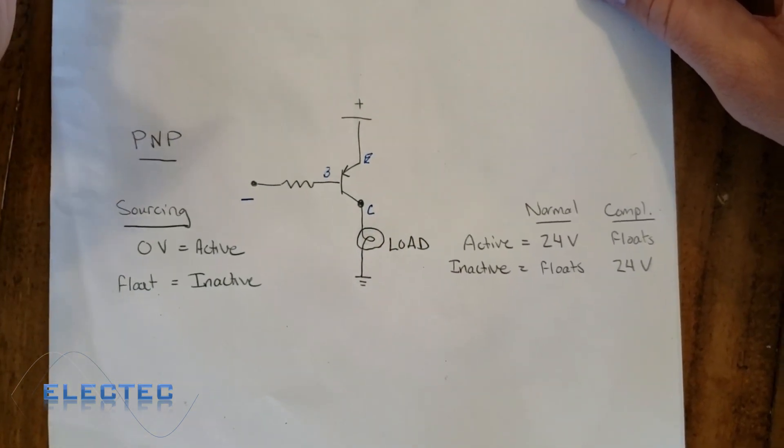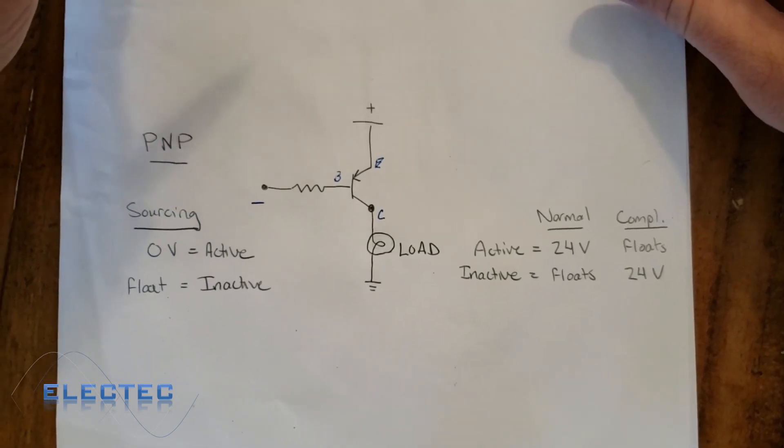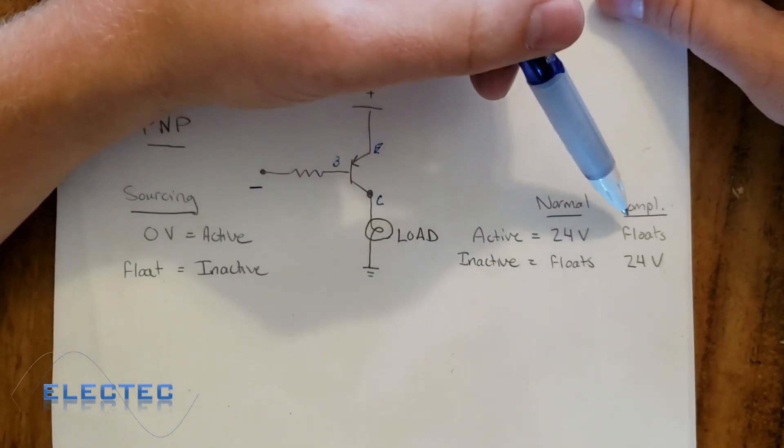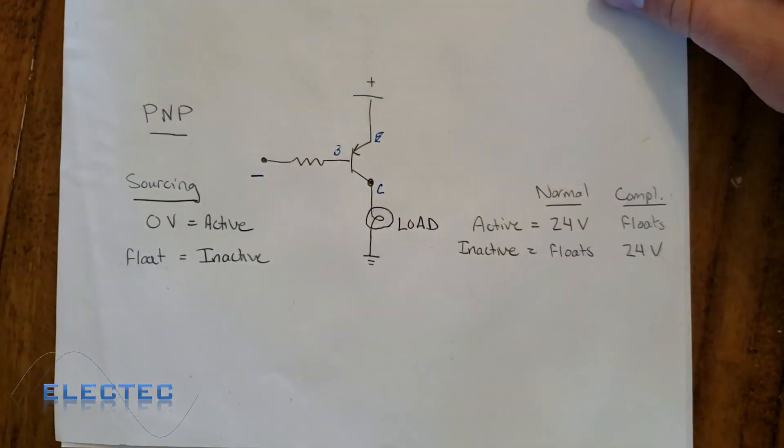So the same thing goes for the complementary, because a lot of sensors have that complementary option. The complementary side is when the transistor is active, it floats, and when it's inactive, it's 24 volts.